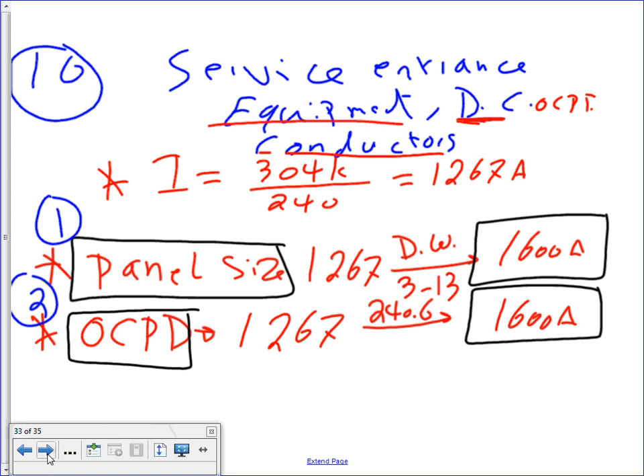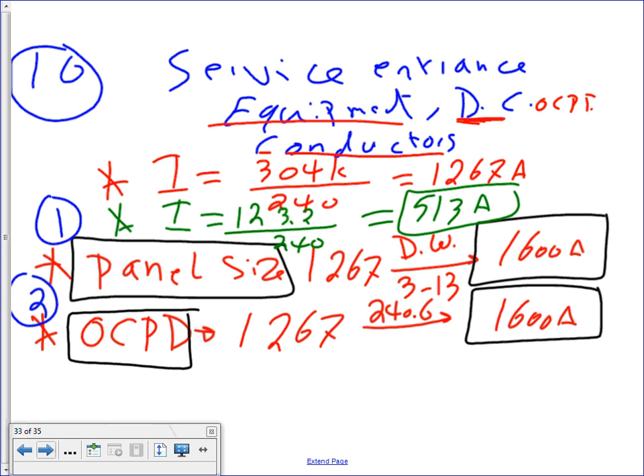Okay, so with the size and neutral, guys, what we need to do, so we got our kVA. Now we need to size the amps. I'm going to do my calculation right here. So I'm going to find I equal, the size that I came up with, guys, 123.2 divided by 240. If you do the math on that one in green, it's going to be 513 amps. That's the amps of your neutral. So you're not going to size the panel or the overcurrent protection device for this amps. You're only going to size a neutral. Okay, so I have 513 amps. Everybody got that one? 513 amps? Yes, no? Cool. 513 amps.